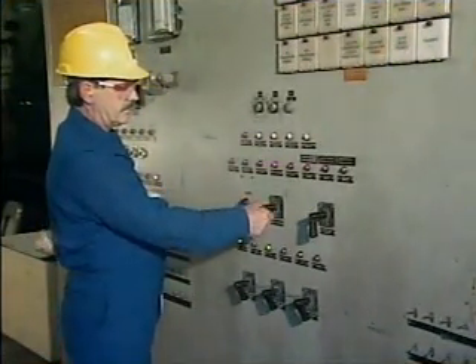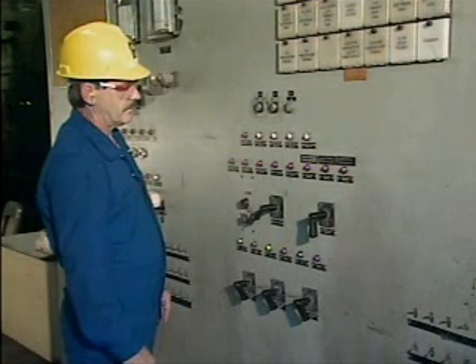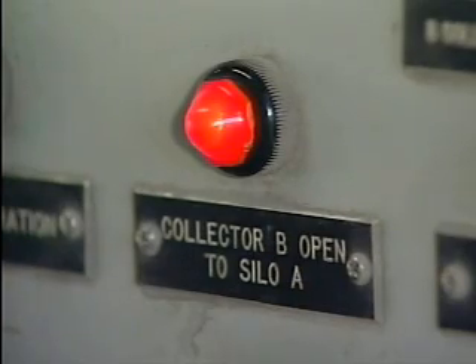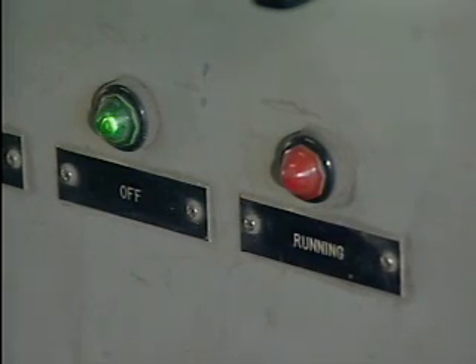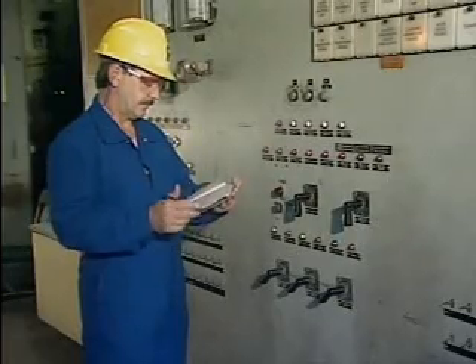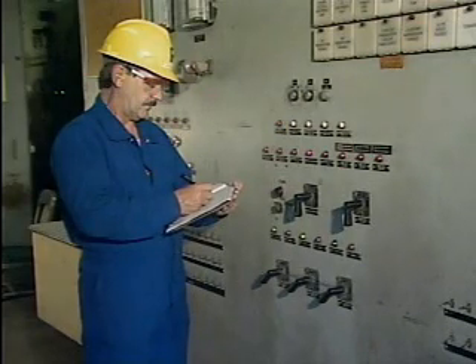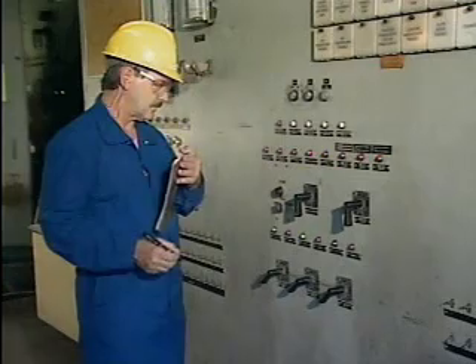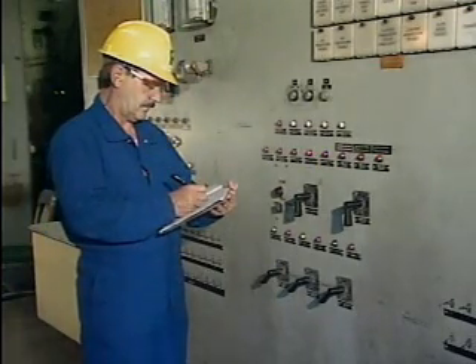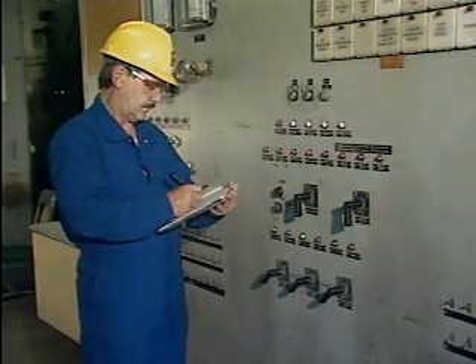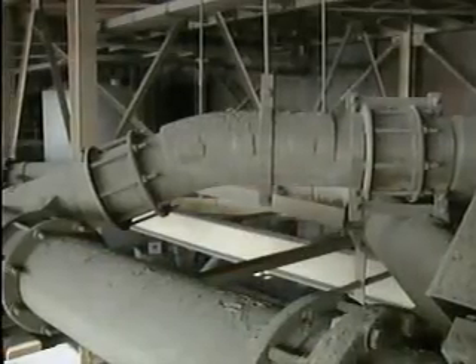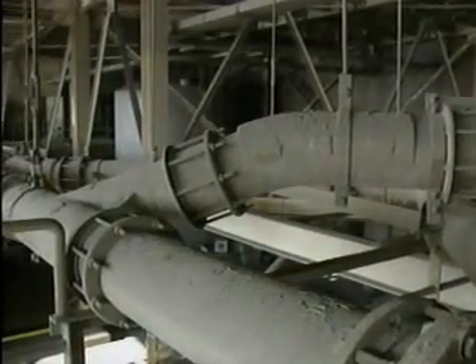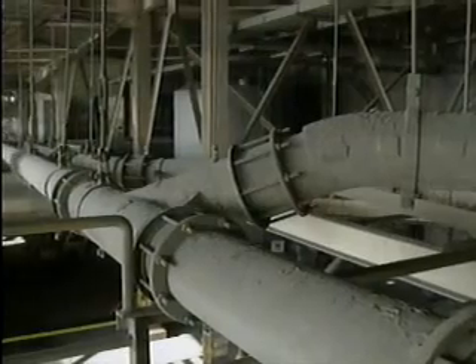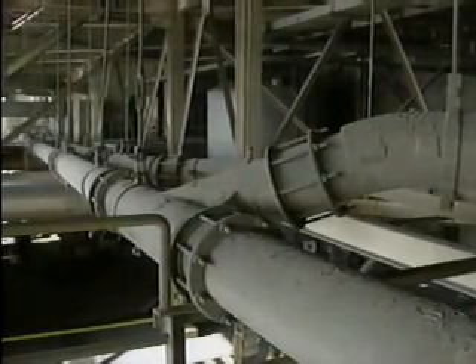At the control panel, the electrician attempts the startup procedure again. This time, the silo crossover indicator light comes on, but the other devices in the process are still not activated. The electrician knows that he has re-established a complete path for the control circuit because the silo crossover indicator light came on. However, that does not mean that there is not another problem in the process. Since the crossover mode is not used very often, it's possible that more than one fault could have developed since the last time it was used.